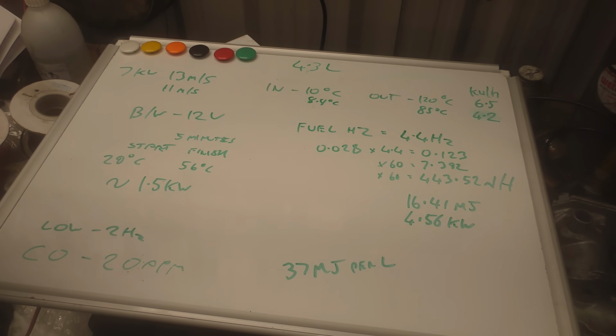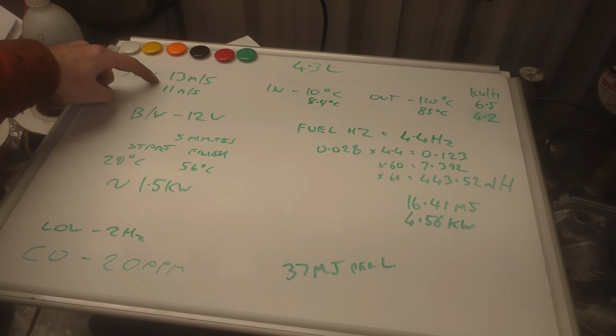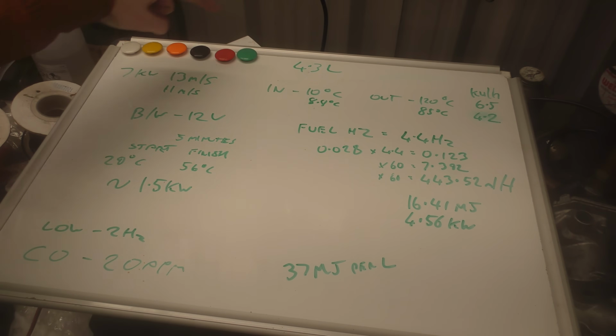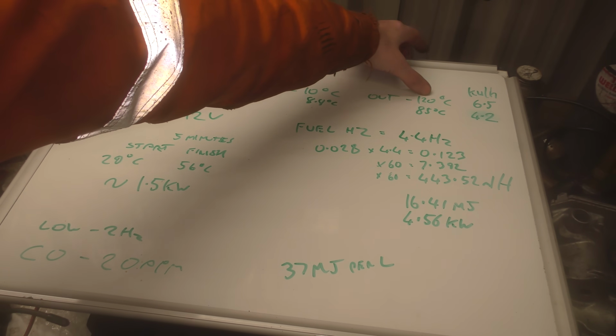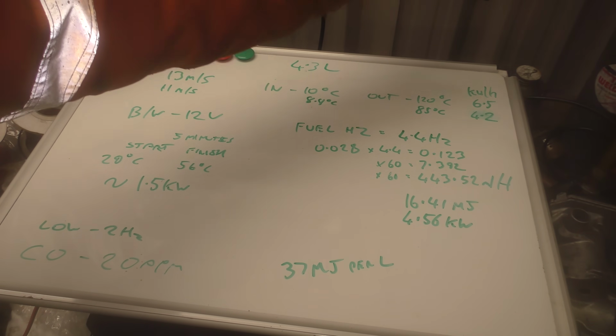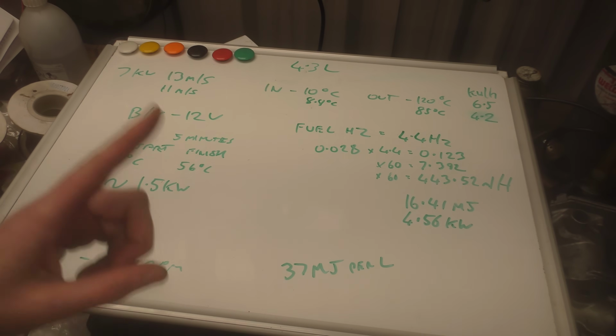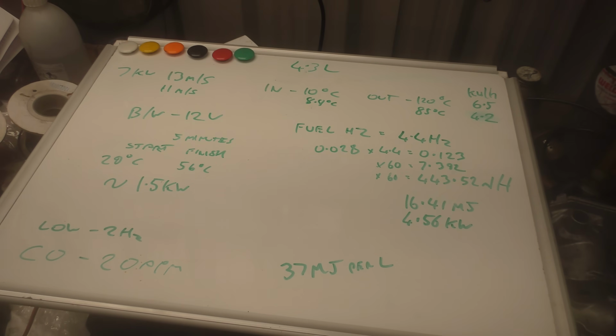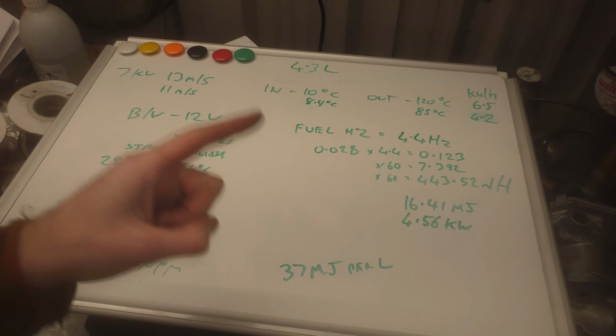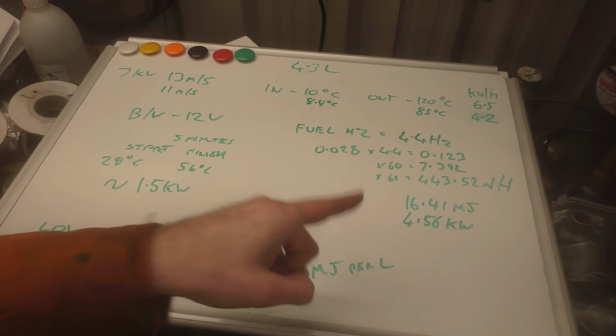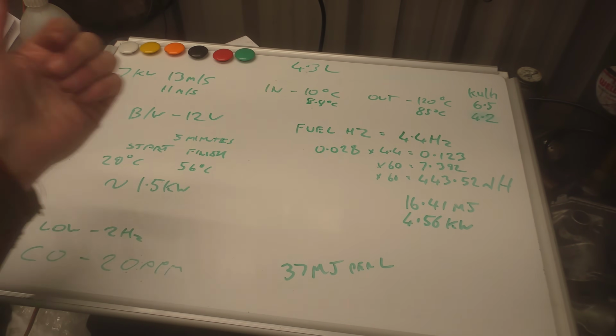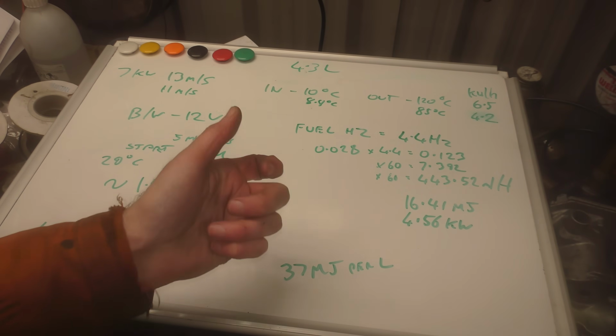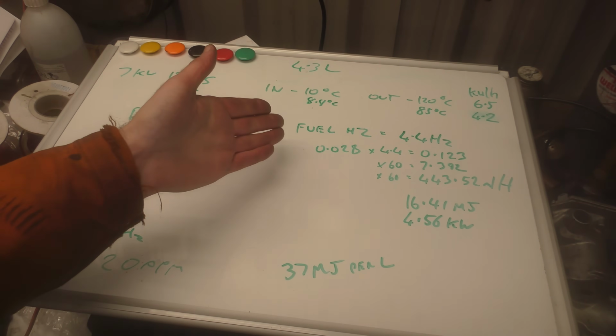So for my first test, I took the maximum airspeed, which was 13 meters a second, an input temperature of 10 degrees, and the maximum output temperature I could find with a probe, which was 120 degrees. That gave the heater an output of 6.5 kilowatts, which is great since it's supposed to be a 7 kilowatt heater. The only problem is that's more energy out than got put in with diesel, because I worked it out using the multimeter in hertz mode clipped across the pump, which measured 4.4 hertz at full running power.